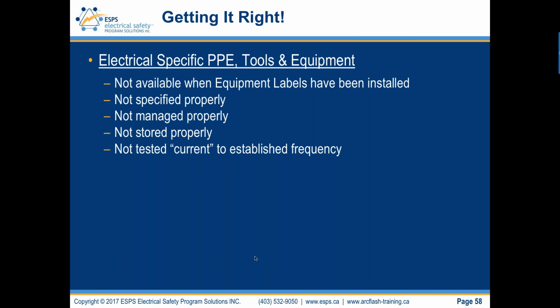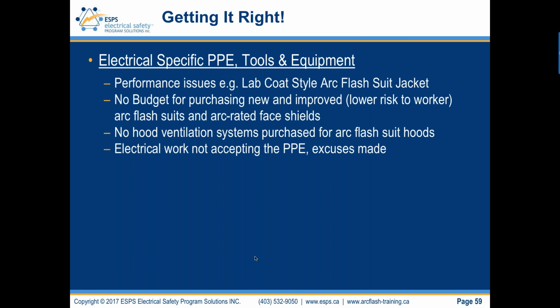PPE requires management, you have to be on it, and it has to be audited regularly. A supervisor needs to audit the arc flash and shock PPE given to the workers at a regular frequency to ensure that it is available, not damaged, managed properly and kept clean. And where testing is required, that the testing has happened and the workers have the latest set of rubber insulating gloves with leather protectors available. Performance issues: the lab coat style arc flash suit jackets that were out there 10 years ago are still out there. We need to get rid of those. When you bend down, the Velcro opens up in the groin area, and if an arc flash occurred, you're not protected. There's no budget.